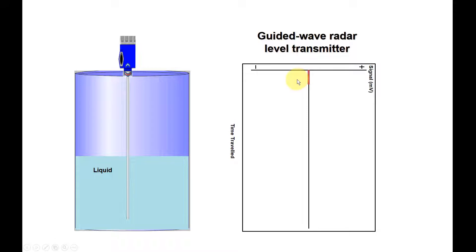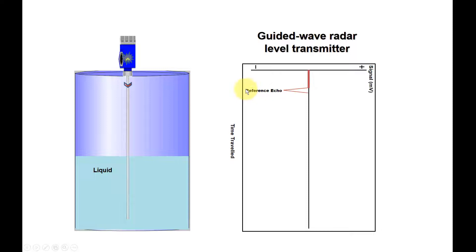You can see the waveform is moving this way too. Then this signal will bounce back and reach the level transmitter electronic board, and it detects there is a radar signal. You can see there's an echo — this echo we call it the reference echo, or reference signal, or reference curve, which is represented by this reference line.